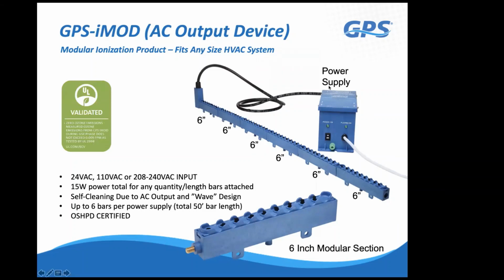This one power supply can power up to 6 of these bars at any length, essentially. Whether it's 20 feet, 30 feet, we can go up to really long coils, but what we have to look at is the maximum bar length. So you could have 5 10-foot bars, which would be 50 feet. You could have 6 6-foot bars at 36 feet. So you get the idea. You just want to keep the maximum bar length below 50 feet if you are connecting long bars to these power packs. It only requires 15 watts of power, and it's available in 24, 110, or 208 to 240. You simply set the switch on this particular model to the voltage that you want to use. If you do use 24 volts input, make sure that it's not floating. We like 24 volts that has a hot and a neutral, and the neutral is actually a grounded neutral, not just a floating neutral like you get out of a lot of control power transformers.